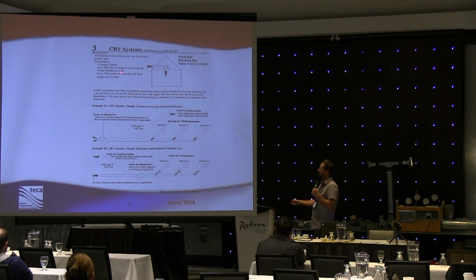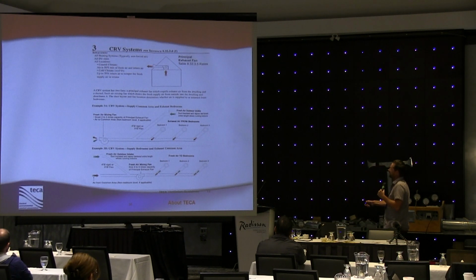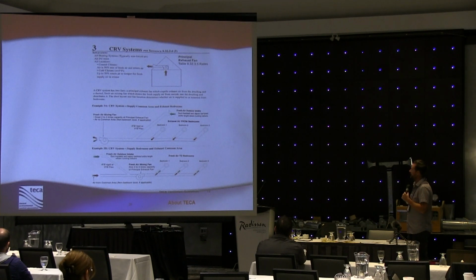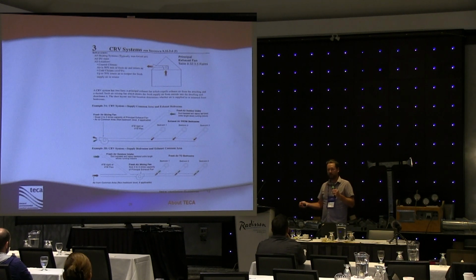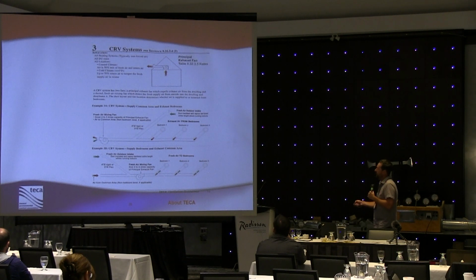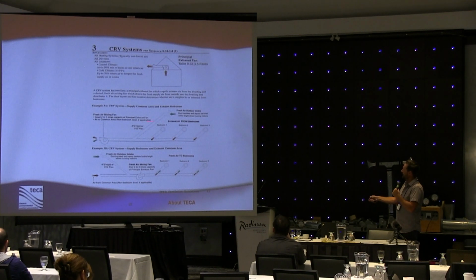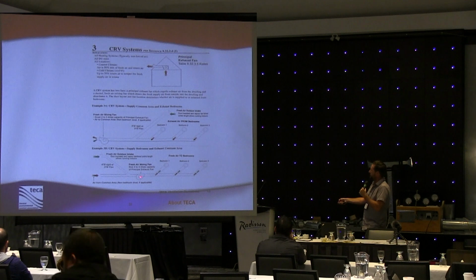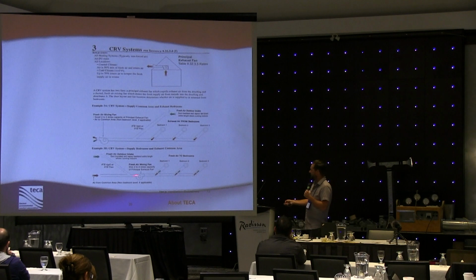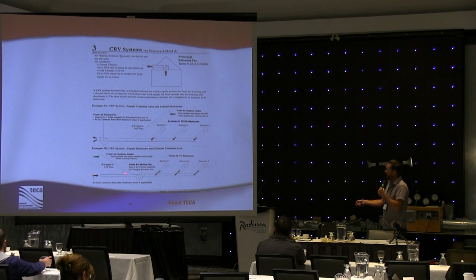Typically, in a coastal climate, I'll explain this a little bit. We have two different applications, a coastal climate application and a cold climate application. The reason being is that you can imagine our wintertime lows on the coast are a lot warmer than they are in the colder climates. So the way the system works is pretty straightforward: we have one fan that's delivering fresh air to bedrooms or exhausting stale air from bedrooms. I can see this methodology going away eventually, but basically we're drawing fresh air in from outside through some ductwork, and we're also drawing stale air in from somewhere inside the building, usually a common area. What happens is we take these two airflows and we blend them together to produce tempered air.